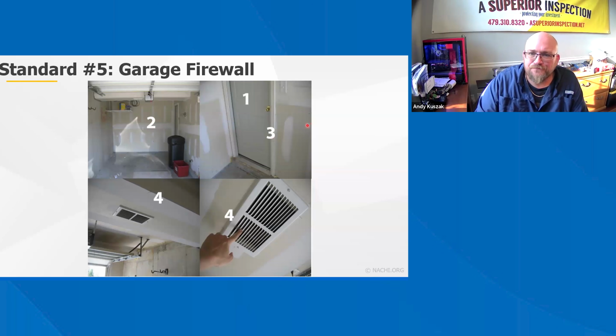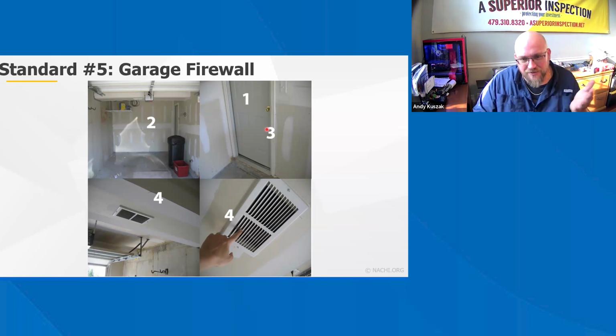And then number three, the type of door construction or the fire rating of the door is important. In many jurisdictions, a self-closing device on the door may be required. The entire door assembly may have to be fire rated. In my area, I'm in Arkansas, they are not enforcing the self-closing latches yet. I think it is coming. We have some builders that do, some that don't, but it is currently not required in my area.